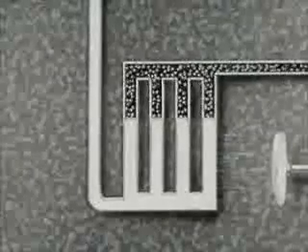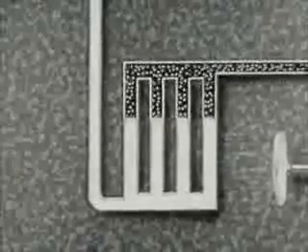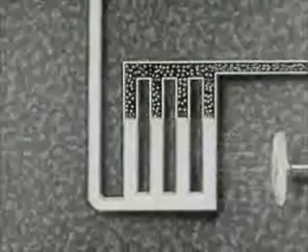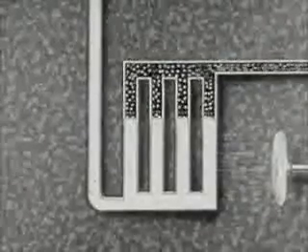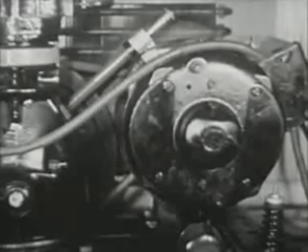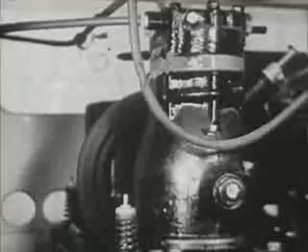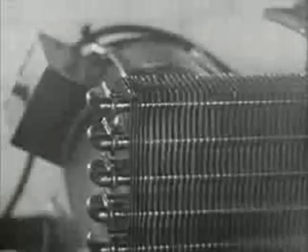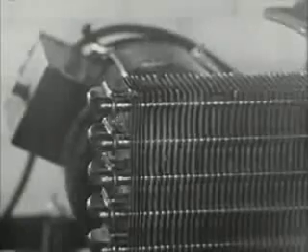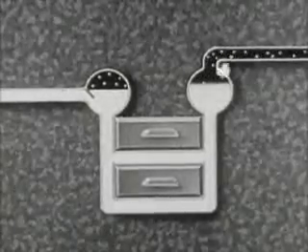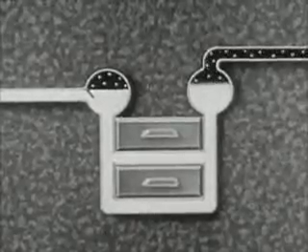In the condenser, heat is withdrawn from the gas by the cooling surfaces. Because of this cooling and the high pressure, the gas molecules condense to a liquid. A fan, also driven by the electric motor, is sometimes used to carry away this heat. Here we see the compressor pump, and here is the condenser with the fan in back of it. The liquid is forced into the evaporator through a needle valve.